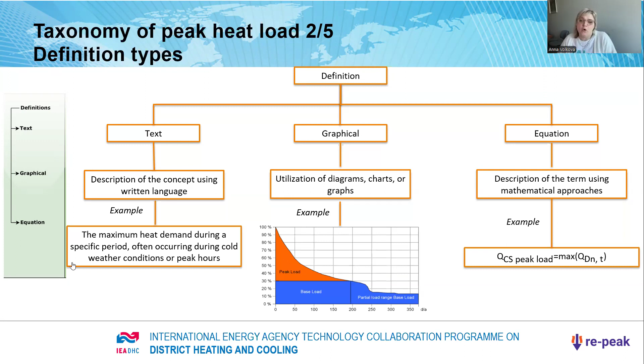A more popular and understandable form of definition for experts is the graphical form, because when you ask any expert in district heating what peak heat load means, usually we start drawing this heat load duration curve, which can be seen on the screen, showing that the peak in the beginning is the peak heat load. Another form of definition available for peak heat load is mathematical equations and approaches, which is extremely important when working with modeling and simulation of peak heat load.